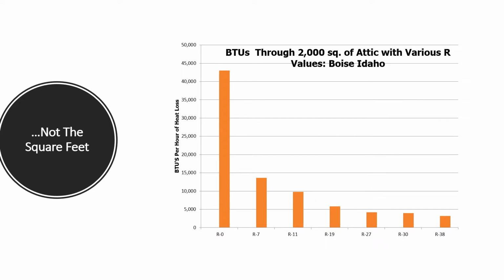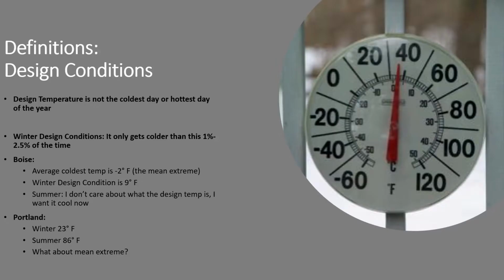So what's more important than the size of the house is the R value, the U value, the heat loss, heat gain. This is another way of looking at the same information. This is BTUs through a 2,000 square foot attic with various R values. Again, we're in Boise. At R0, oh my gosh, 42,000. That's a gas furnace all by itself. By the time we get down to R7, we get a big jump down, and at R38, boy, we're much lower. This is not to say that high R values aren't important. Why not stop at R11? This is to say when it comes to sizing of equipment, the biggest differences come when you make a low R value higher.